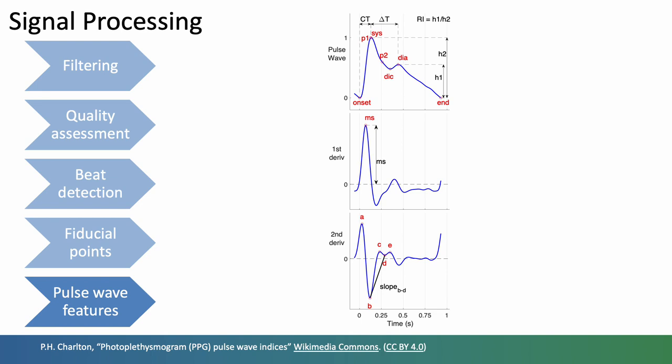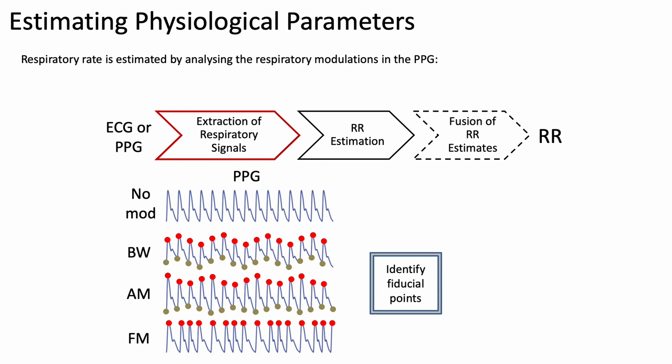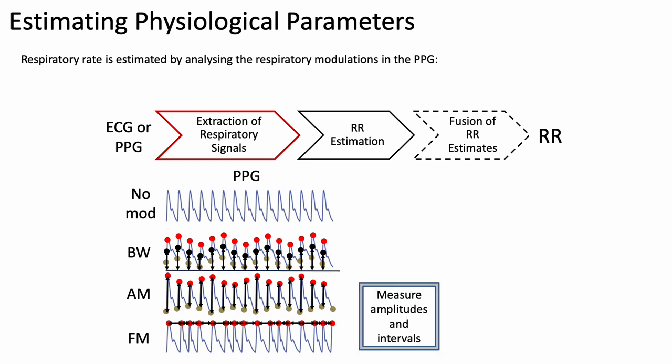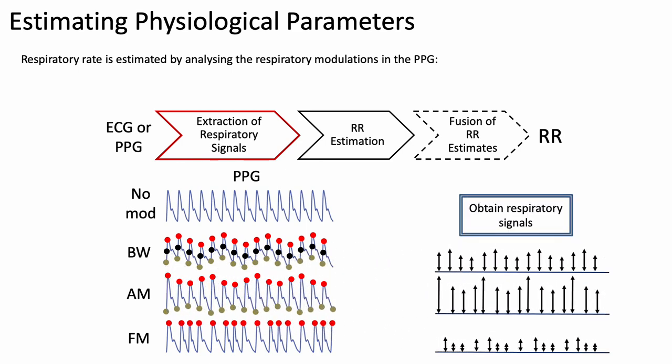I'll give you a few examples of how this process is used to estimate physiological parameters. Firstly, estimating respiratory rate. Respiratory rate algorithms typically consist of three steps. Firstly, the extraction of respiratory signals which is done by identifying fiducial points on the pulse wave and finding the baseline, finding the amplitudes and beat to beat intervals and using these as surrogate respiratory signals where ideally the signals exhibit one peak per breath.